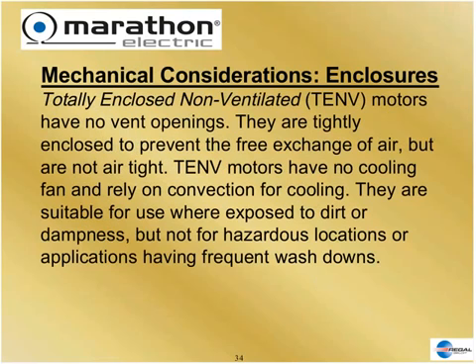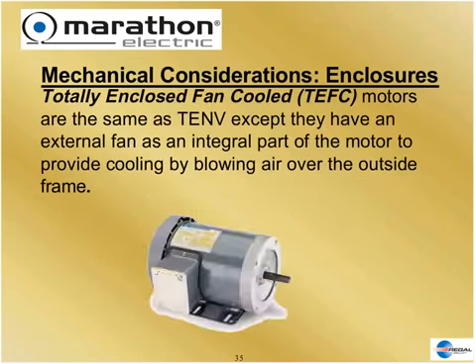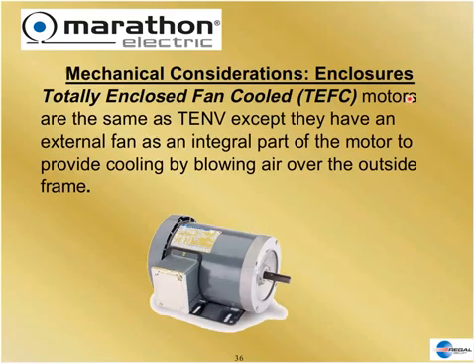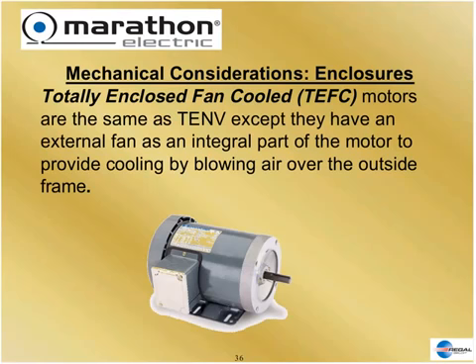Sometimes the environment is not conducive to having air go inside the motor — it might be wet, dusty, caustic, or even volatile. So we have to make motors non-ventilated. A totally enclosed non-ventilated motor has no ventilation whatsoever, so it can be used in harsh environments, but it must be designed so heat convects from the frame — not as efficient for cooling. On an enclosed motor, the most efficient approach is to put a fan on the outside to blow air along the frame and wick heat from the center.